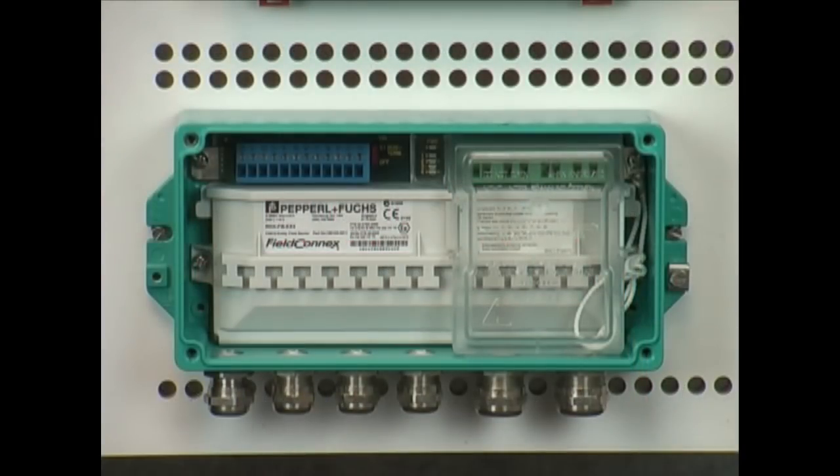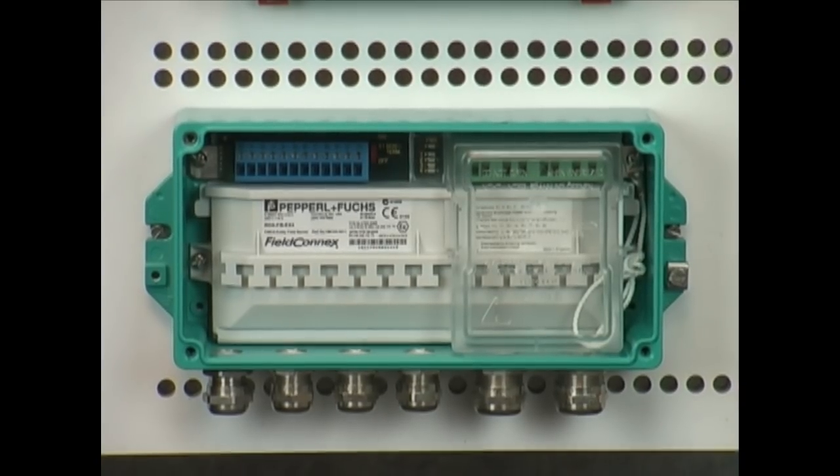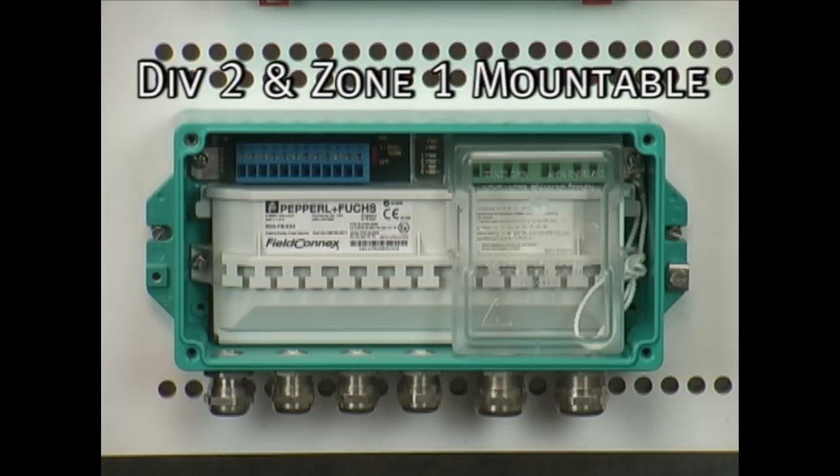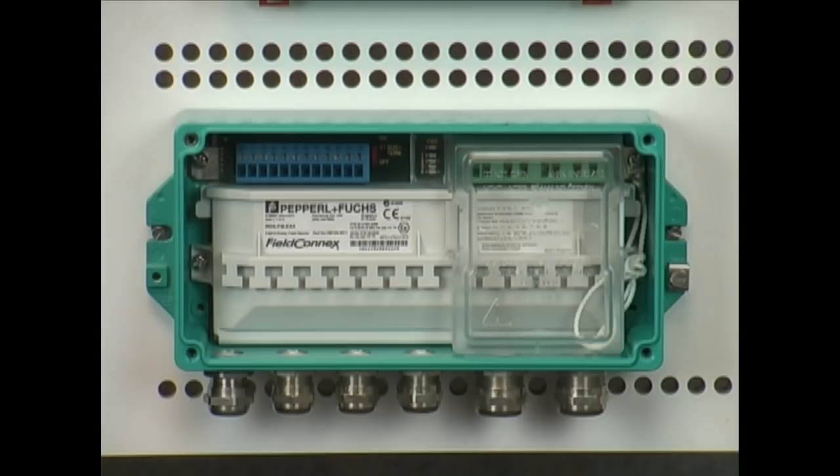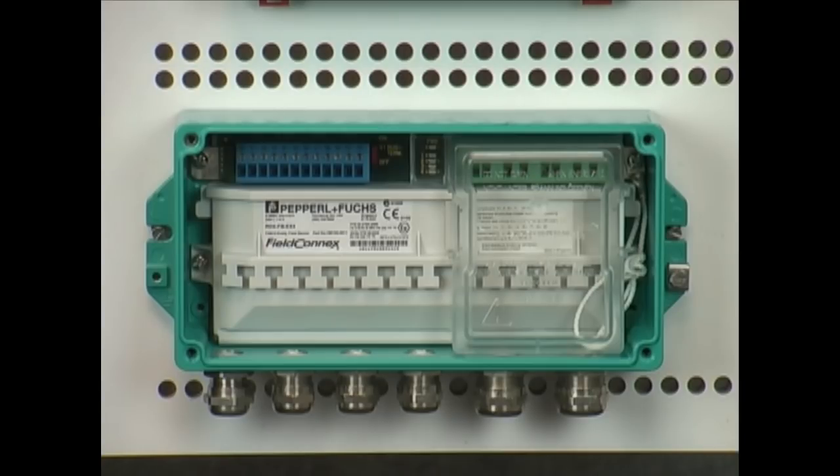Another option for field distribution when using the high power trunk concept is the field barrier. This is a Division 2 mountable, Zone 1 mountable interface that provides you with four intrinsically safe outputs for use in Class 1 Div 1 or Zone 0 applications. It provides again short circuit protection for the individual spurs as well as the optional terminator.